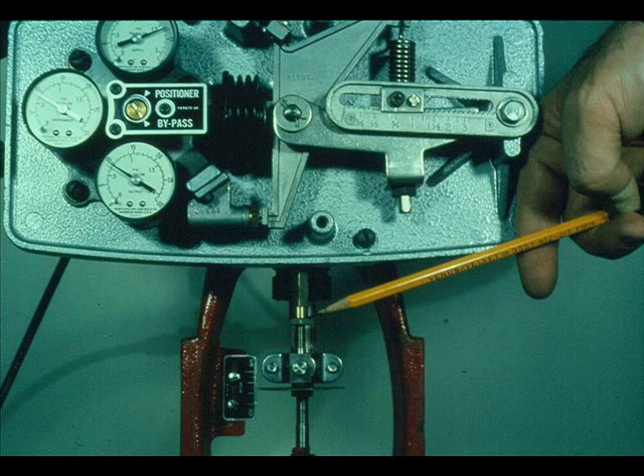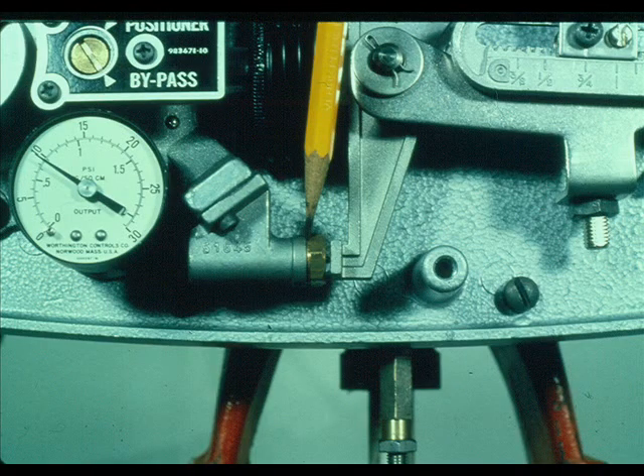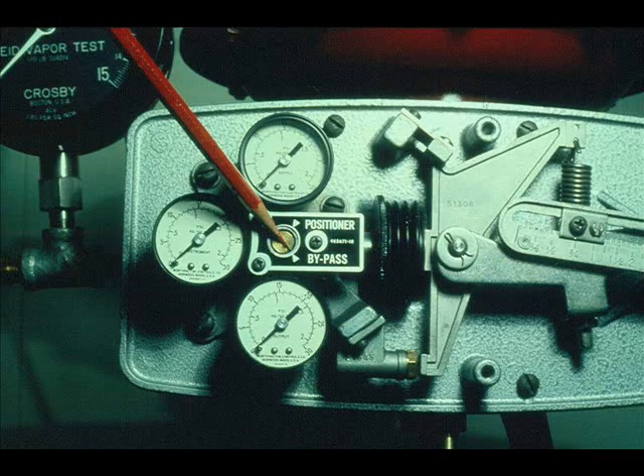This is a Masoneilan model 7400 valve positioner. It is a force balance device. The zero adjustment is made with the turn buckle. The span adjustment is made by turning the pinion, which moves the index left and right on the stroke scale to make the positioner output agree with valve stroke. The Masoneilan 7400 can be split-ranged, but you have to have a reverse-acting pilot to change the action. This is the bypass.